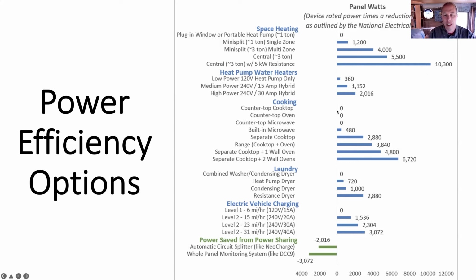The same goes for water heating, cooking, and laundry machines, say for a laundromat. There are so many ways of pursuing power efficiency if that's the issue. Since there's this unpleasant conflict between PG&E and the San Francisco PUC over infrastructure upgrades, when electrifying an existing building it'd be really easy for everybody if you didn't have to ask for a larger transformer, saving time, money, and sheer emotional frustration in the engineering designs. So power efficiency, which comes from better design and better equipment, is something to study and work on with your electrical engineers. Don't just accept that you have to put in a big transformer and that it's going to be long and hard.